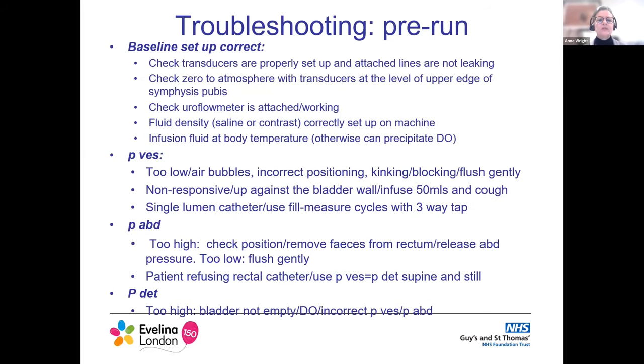In terms of troubleshooting before you run your study — like any surgeon, like any pilot — make sure everything is set up correctly. Check everything's connected correctly, correctly set up, zeroed at the correct level, and that your uroflowmeter is using the correct density on your machine, because saline is lighter than contrast. Make sure your infusion fluid is at body temperature — if it's too cold, it can precipitate detrusor overactivity.